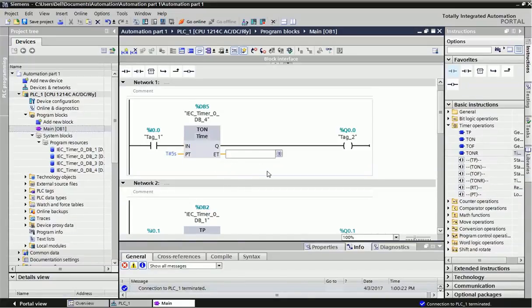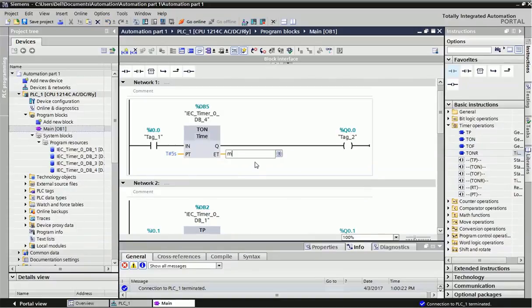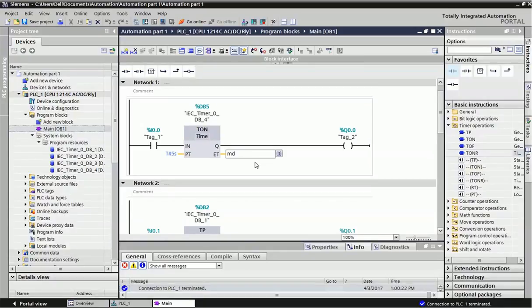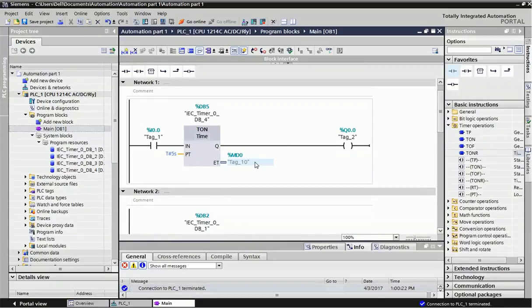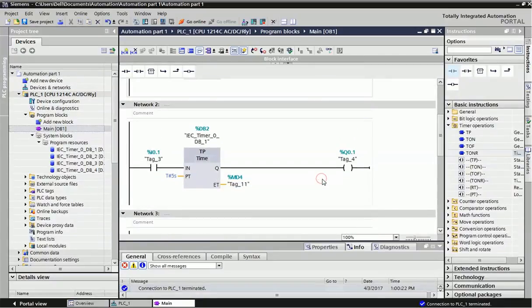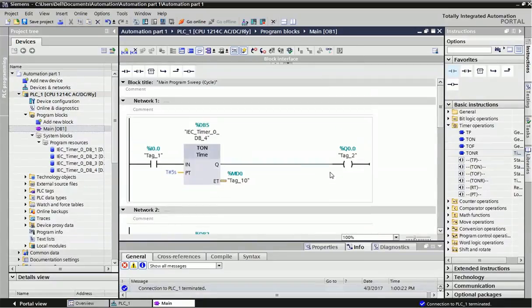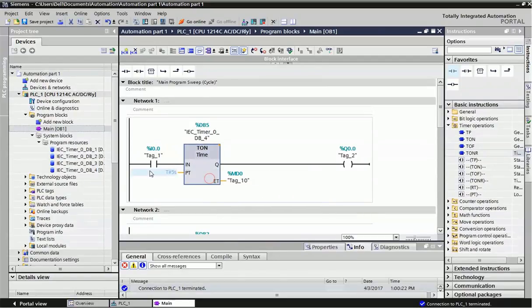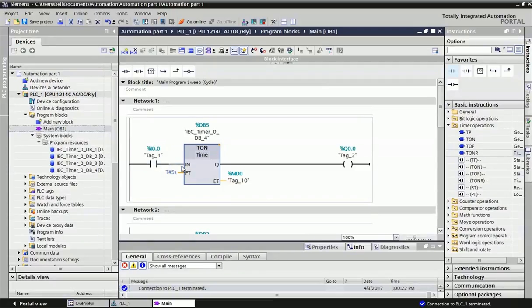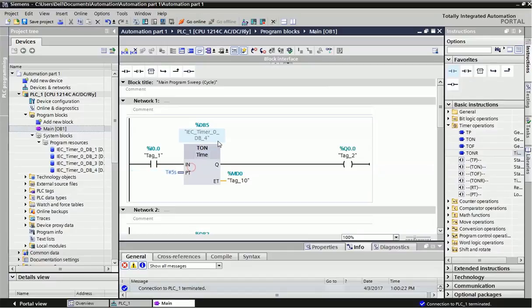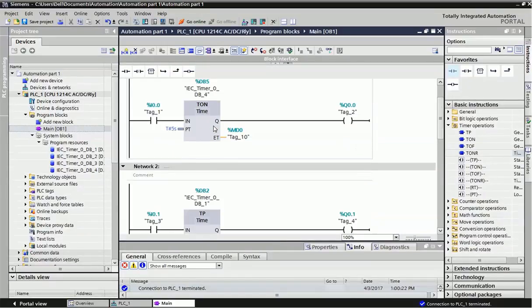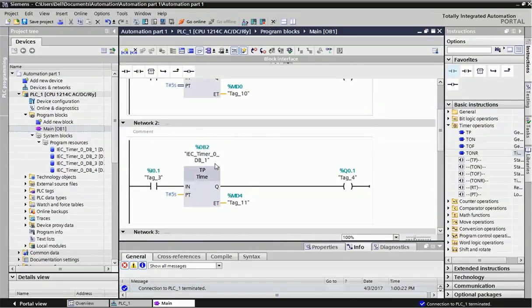Elapsed time is displayed when the timer is started, and that value is updating. If you want to display the value, you need to give memory double word, because this time data type uses 32-bit stored memory. I'm giving MD0 to store the data. For TON, after five seconds the output will be on. For this timer, the input should be continuously on. When the input is off, the timer will be reset.